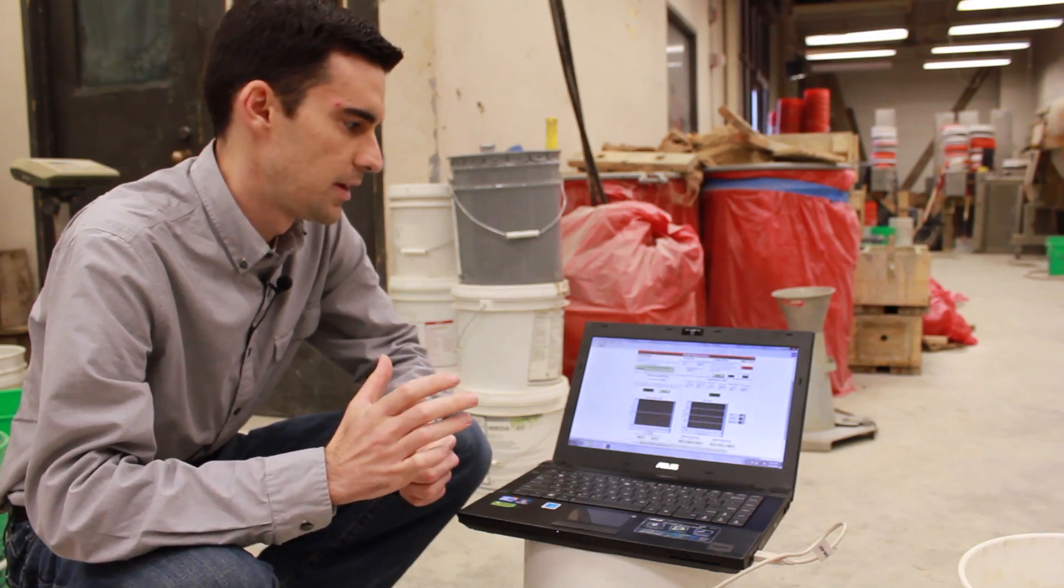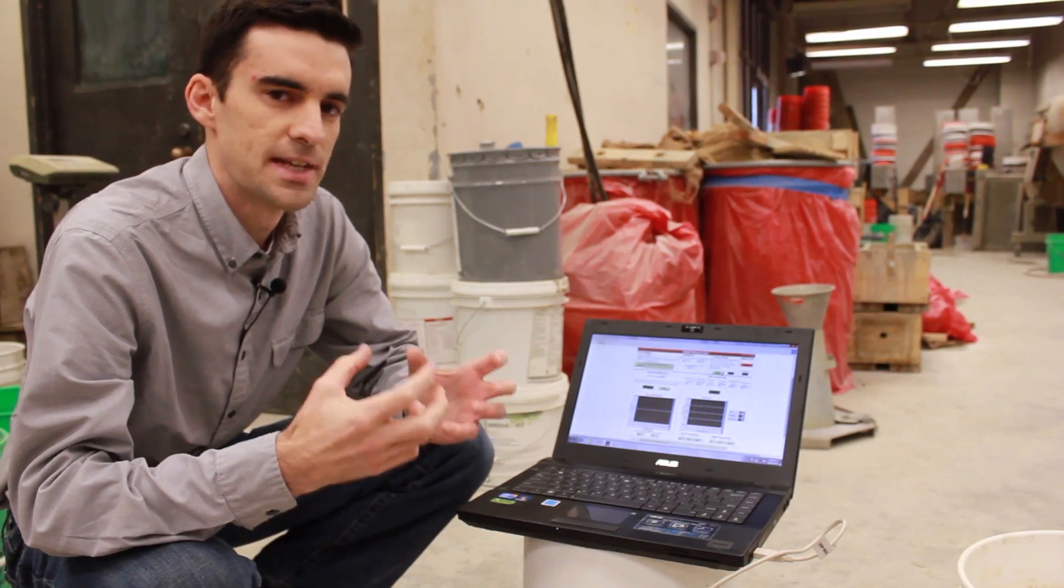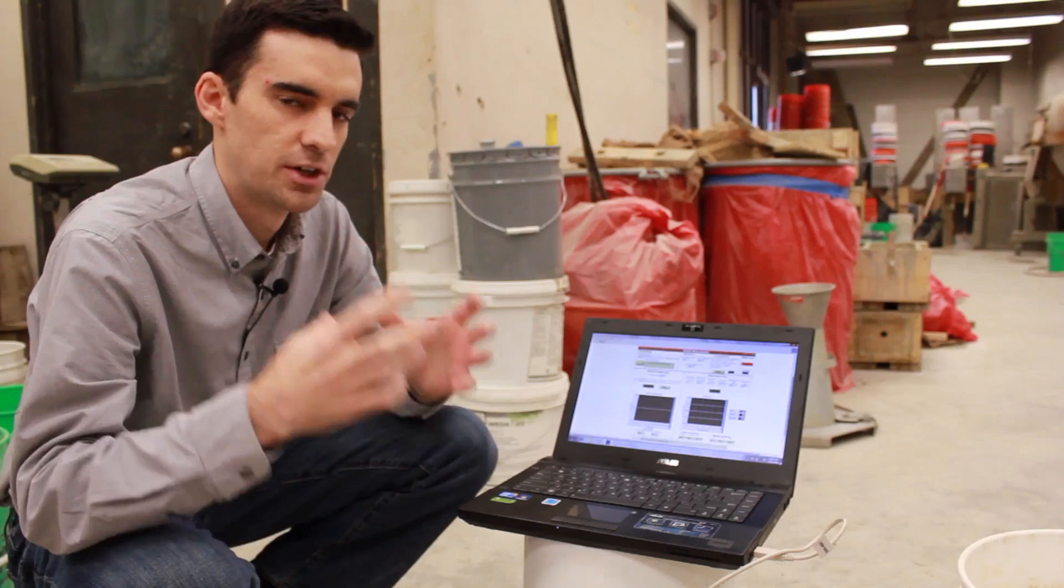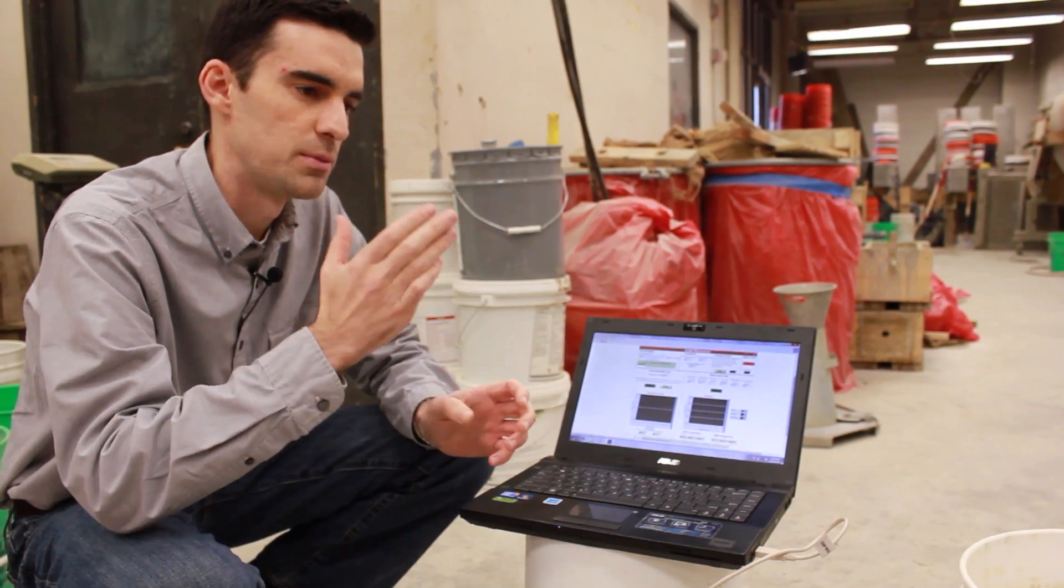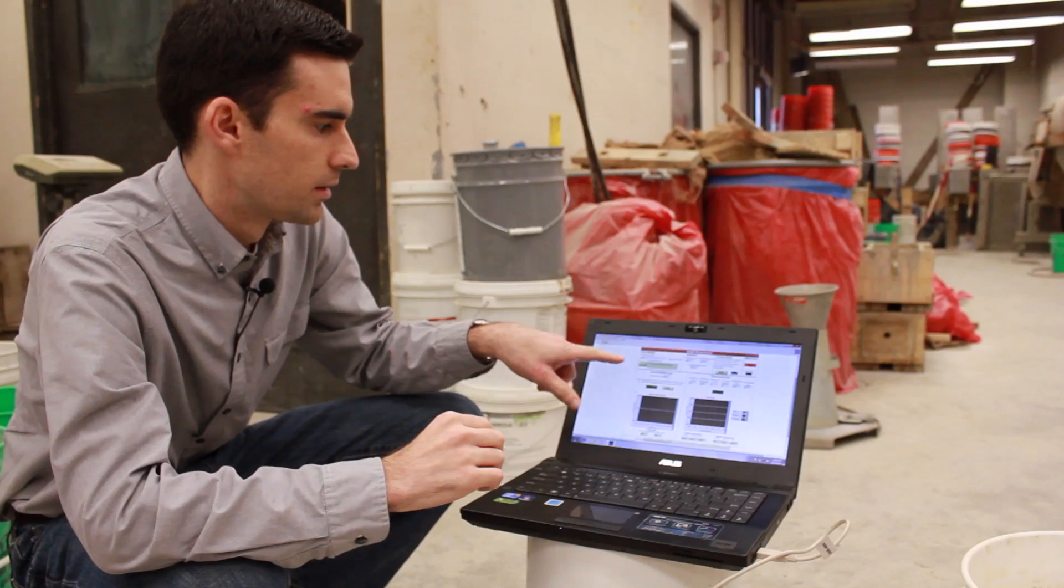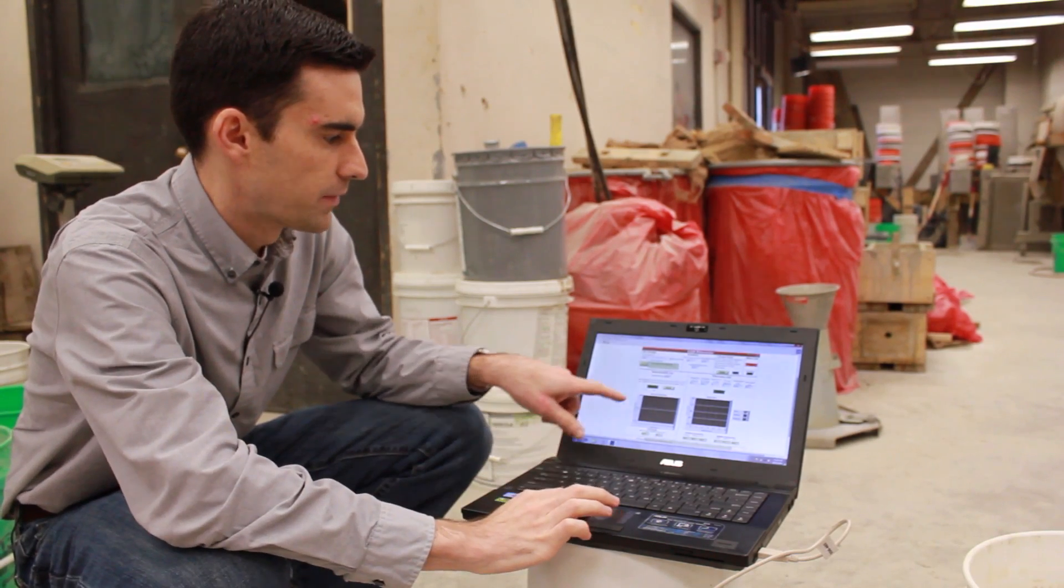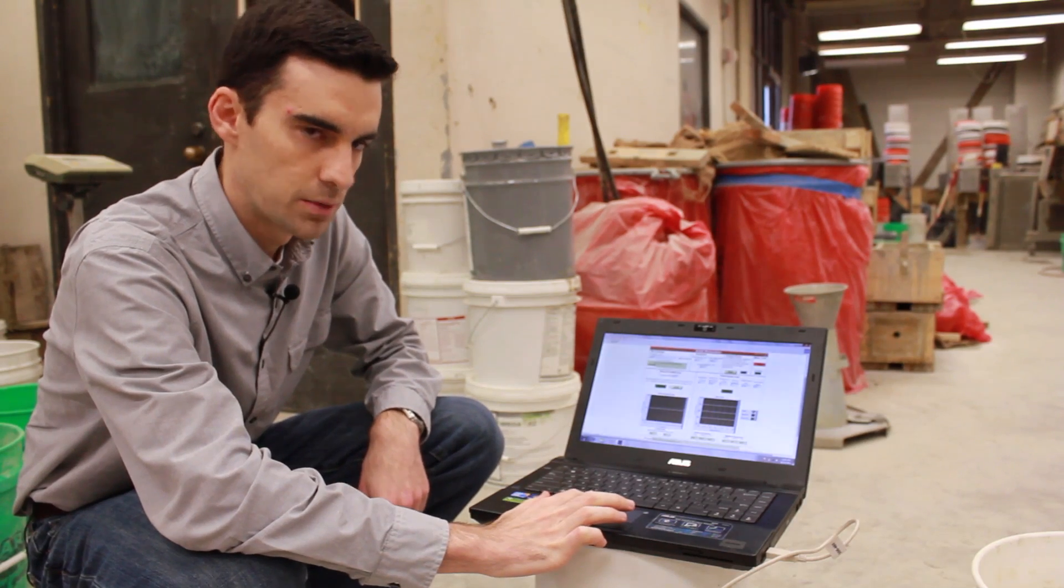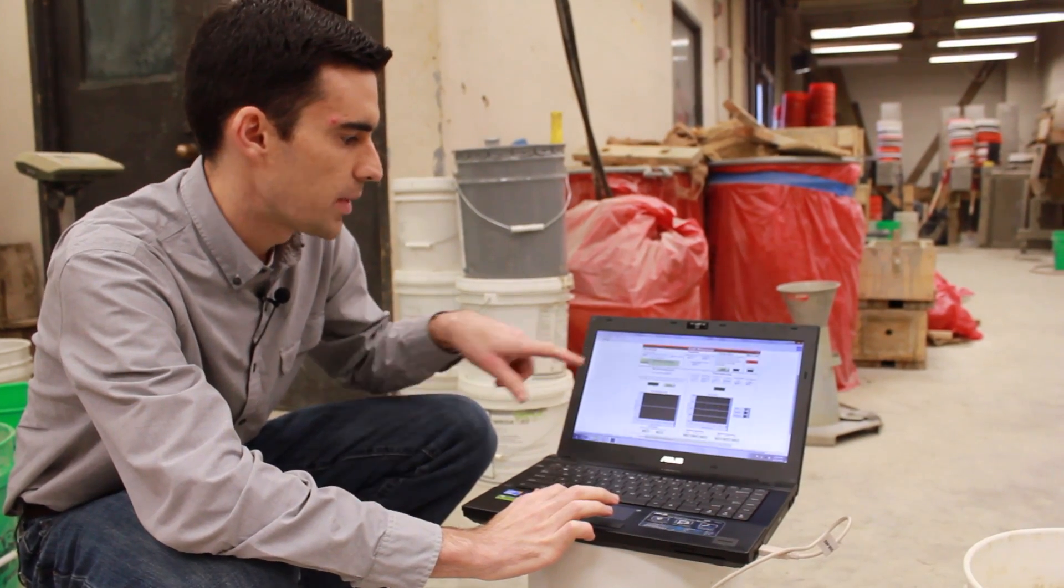We'll start with the stress growth test. The stress growth test measures the static yield stress. So it's very important that we have a consistent shear history. In other words, the time since we've filled the container until the time we start the test should be consistent in order to compare two or more tests. The software is already set up to operate at 0.025 revolutions per second, which is the speed we want. So all we have to do is press start.